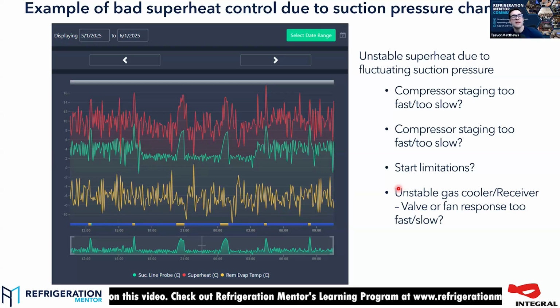I'll give you an example, Kevin. What would you set your lowest minimum gas cooler pressure at, to make sure you're maintaining? I generally don't like to go much lower than about 50 bar. Apologies, I don't know what that works out to in PSI off the top of my head, but so like 750, I think it is.